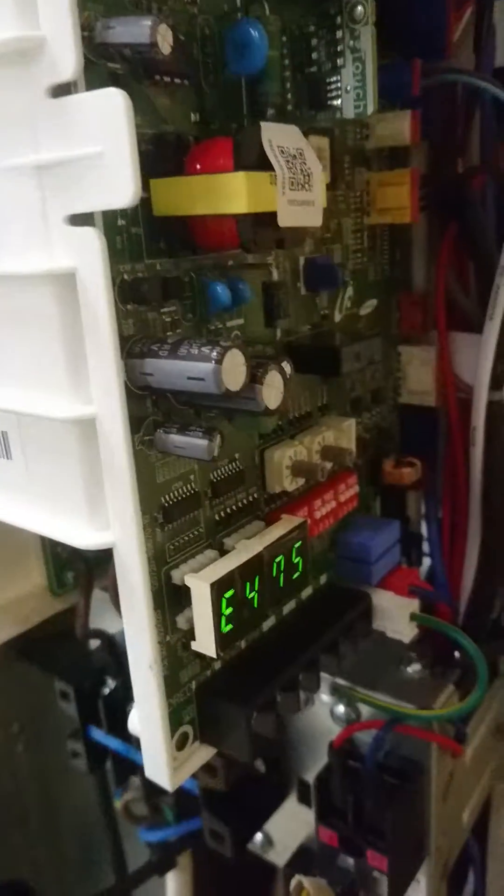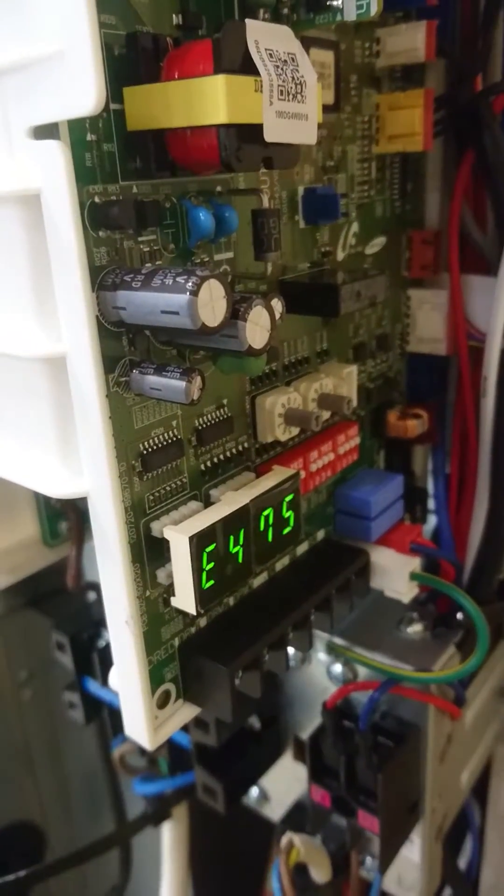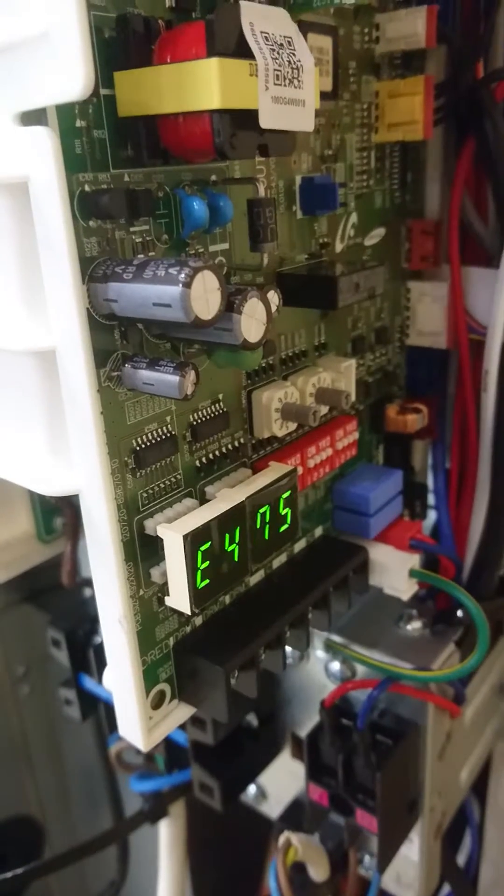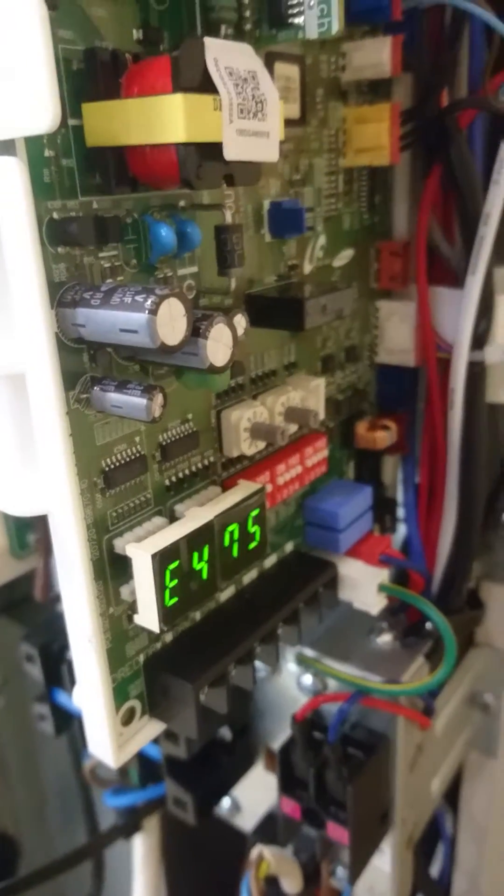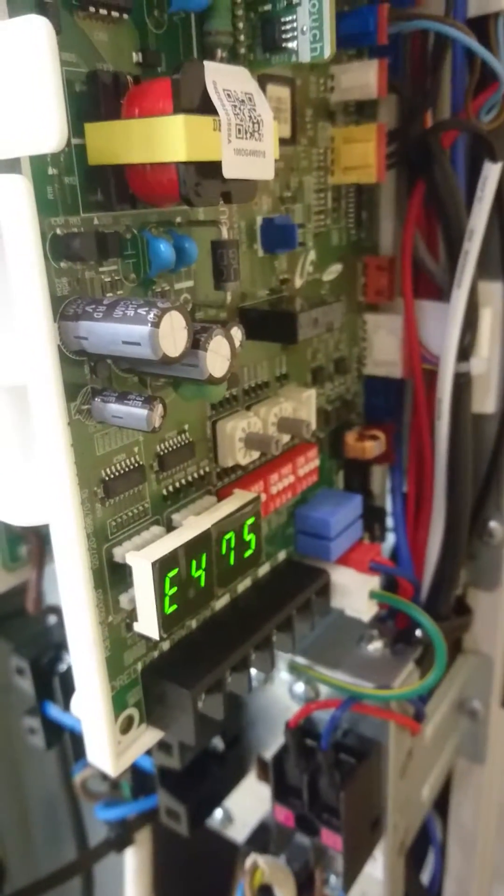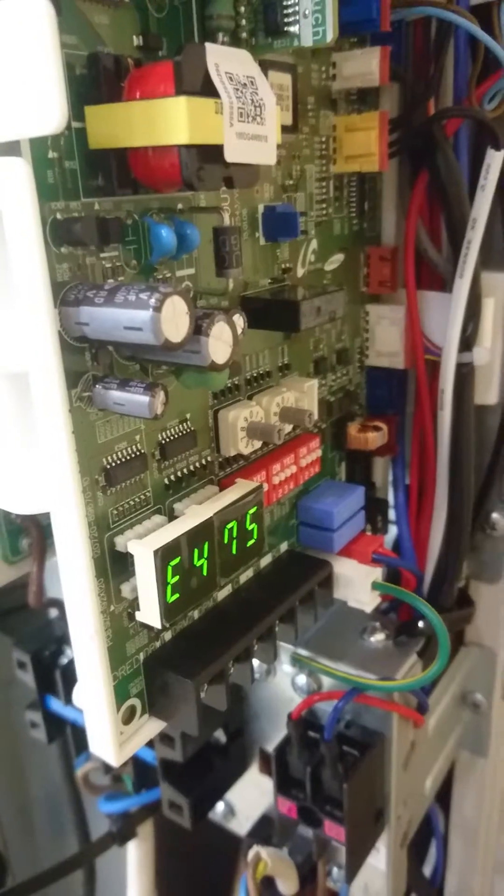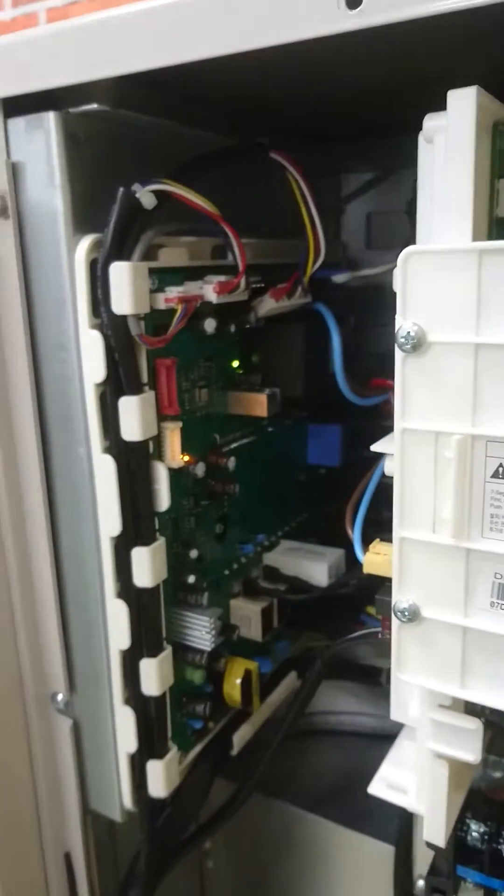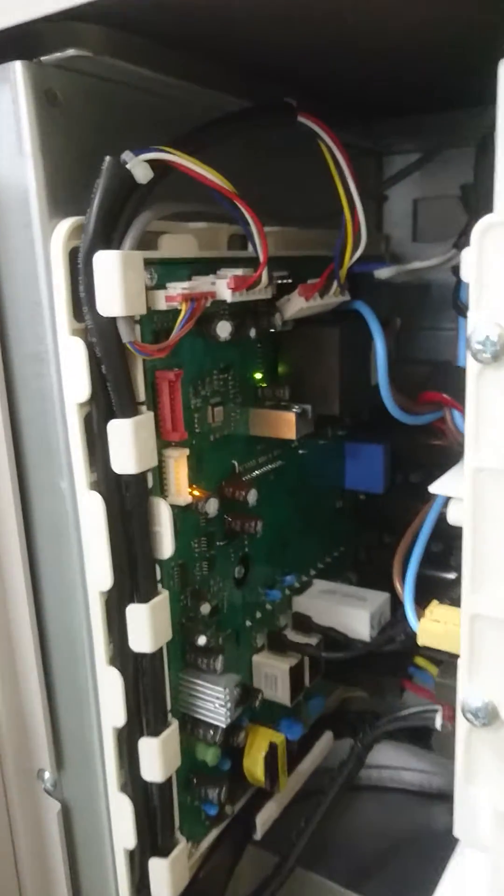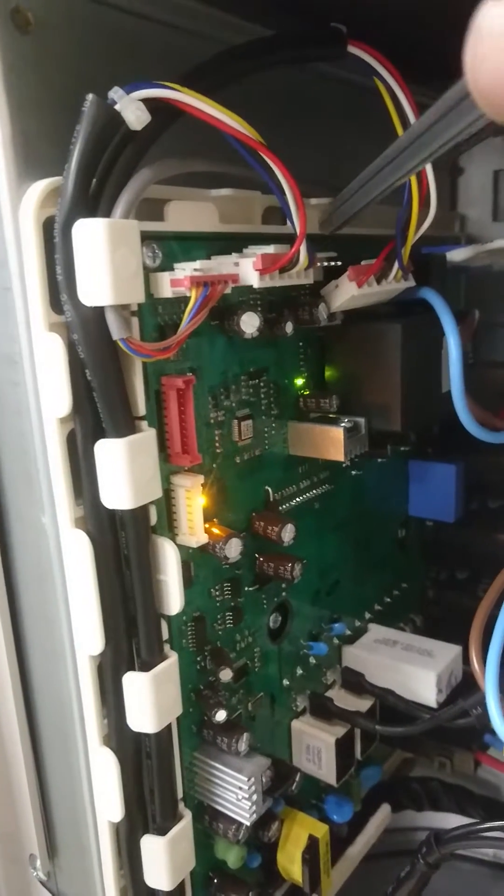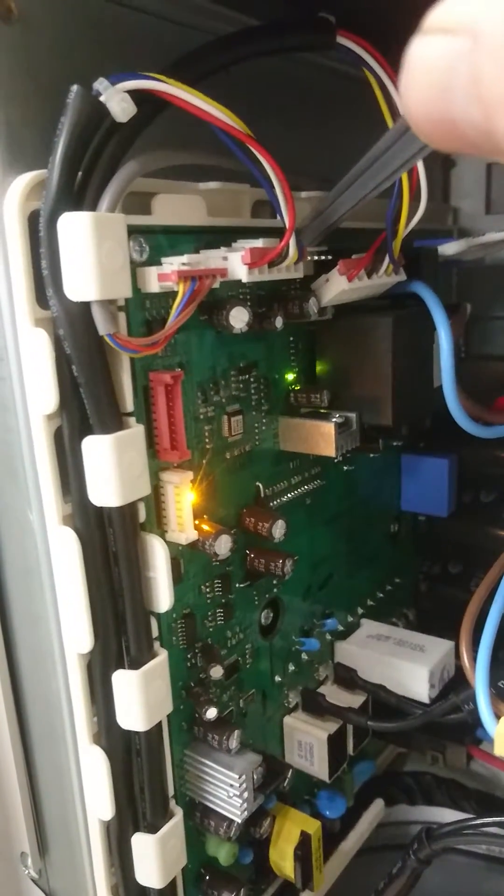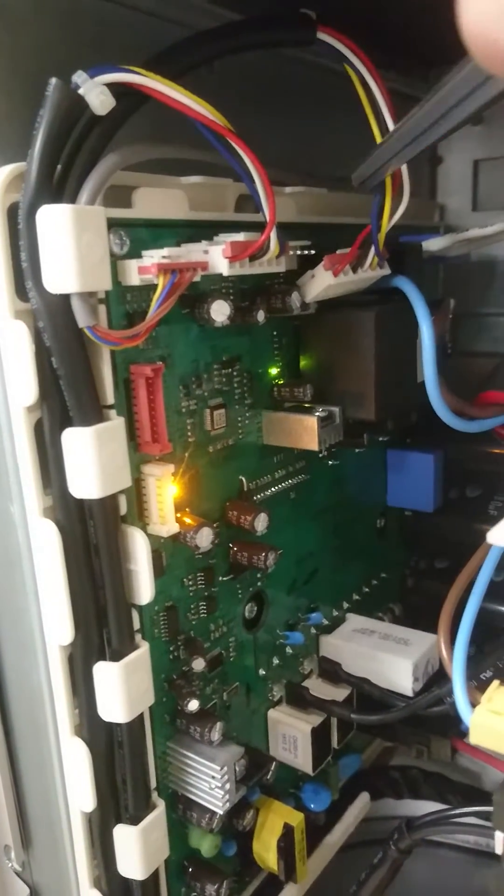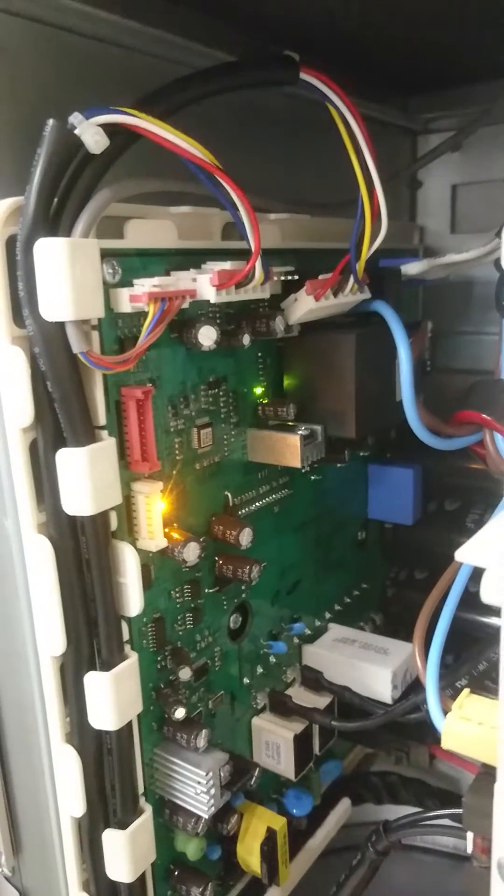And if we look over here, you can see E475 on the error display. 475 means that something has gone wrong with the top fan motor. And when you look on your inverter PCB here, the top fan motor is the back plug here. I've unplugged it to show the fault code.